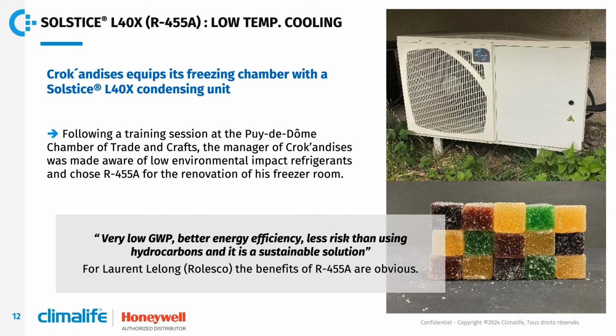A third example with the use of R455A for an independent small store, which equipped its freezing chamber of about 12 cubic meters with a condensing unit working with R455A. And again here, as you can see, the manager of this store is very happy with this solution because it provides low GWP, better energy efficiency, less risk than using hydrocarbons, as well as sustainability.